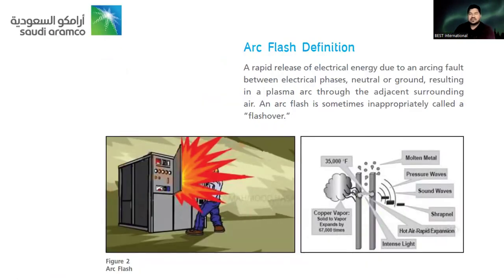The arc flash definition, since I asked you earlier, is a rapid release of electrical energy due to an arcing fault between electrical phases, neutral or ground, resulting in a plasma arc through the adjacent surrounding air. An arc flash is sometimes inappropriately called a flashover. So look at the picture, Figure 2, arc flash. You can have an understanding of how it can happen.